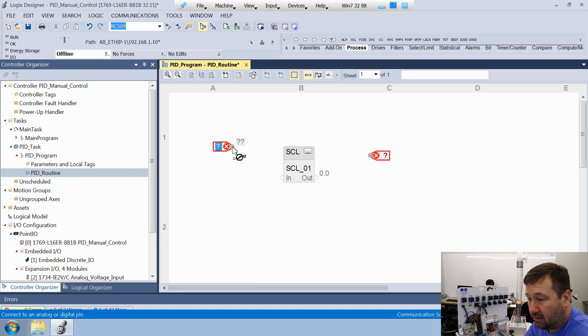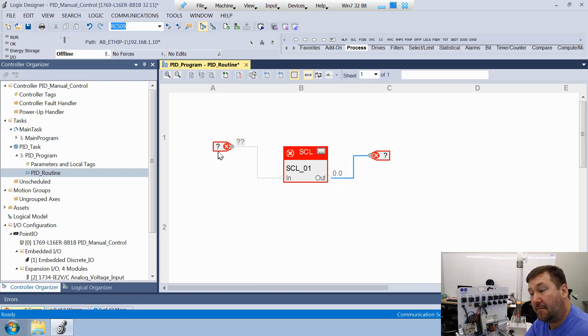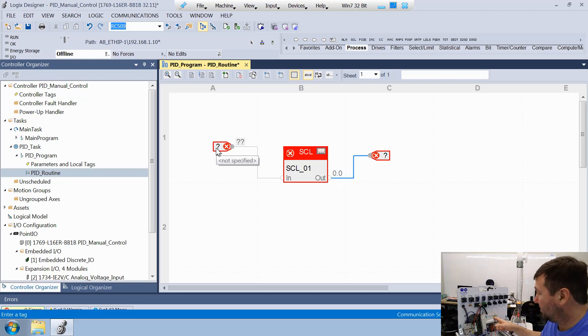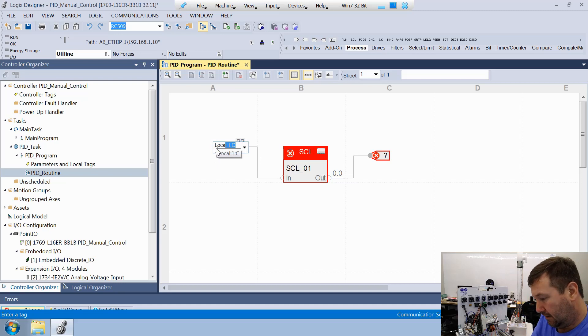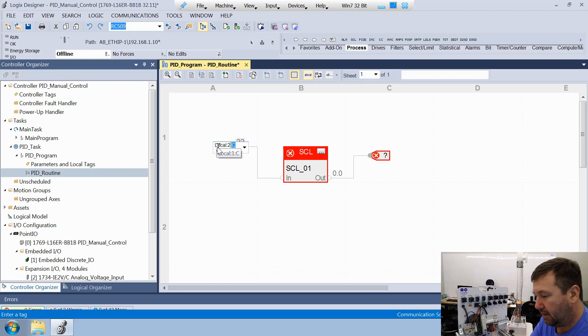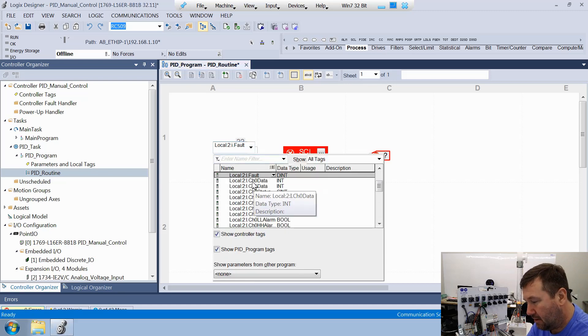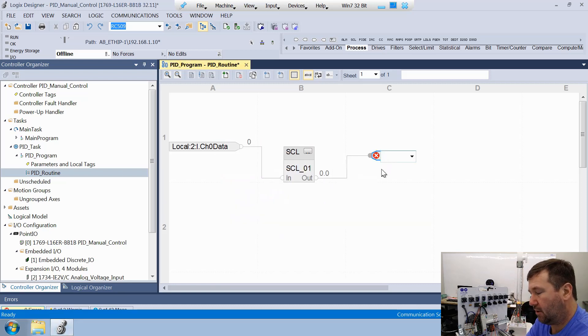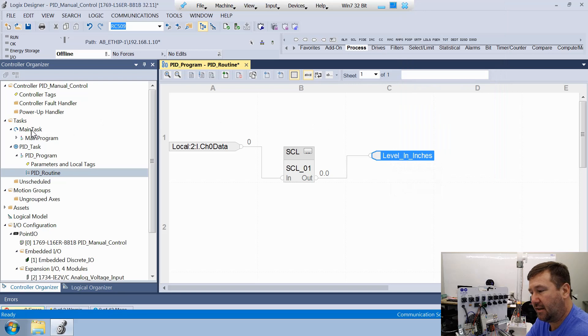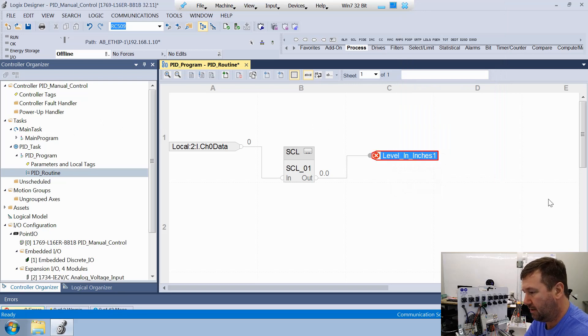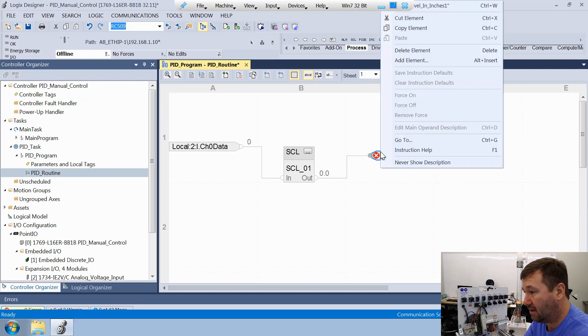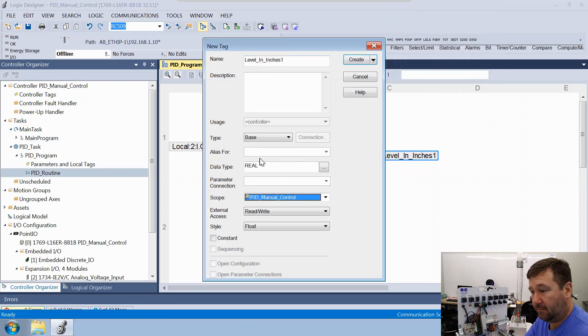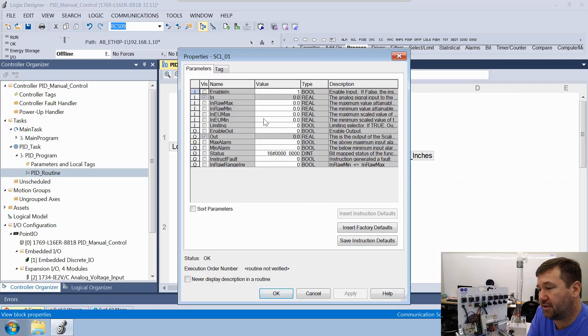You'll see there's a little dot there that turns green when you mouse over. When it's green, click on it, and let's drag that over to our input. Let's drag this over to our output. For our input, it is going to be the raw data off of channel zero of our analog voltage input. So we're going to go for local:2:I.data. We can bring this down if you're not sure. We're going to be looking for channel zero data. Then for our output, we're going to use level sensor in inches, which is a tag I already created. Just to show you how, let's make level in inches one. You see now it has a red X. That's because it hasn't been created. So we'll right click it and click new. Then we want data type a real. That's how you would create that.